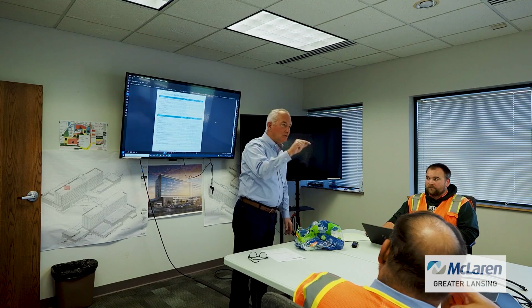I said, after 45 minutes, Joe, what's the temperature of the condenser water going to the chillers? He says, 79 degrees. He says, I need it to be 78 or lower, or the chiller goes off on high head. And I said, Joe, the cooling tower is only going to deliver 85 degree water on a design day. You have a condenser problem. If the cooling tower is making 85 degree water, the control system probably has it set up to make colder water than that, and it's able to do that almost the entire year. However, on a design day where the chillers are running fully loaded and the wet bulb temperature is 78 degrees, we're going to get you 85 degree water. This isn't going to happen probably in our lifetime either.